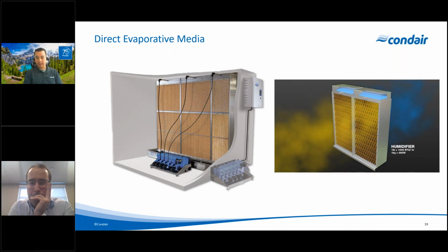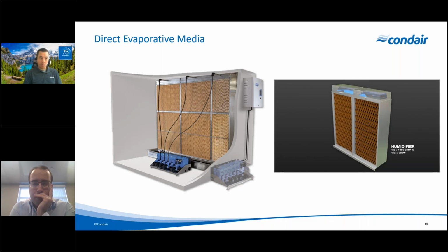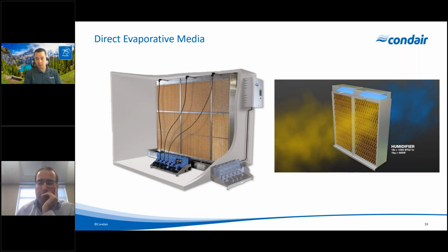But in terms of operation, water quality, and install, this is probably the most basic system that you can use when we're looking at adiabatic. The nice thing about it is, because it's an evaporative pad system, we can use any type of water. As long as it is drinking quality water, you can put the water through the system. And because all of the evaporation takes place within the pad itself, generally for a retrofit application, we don't need as much room as we would with, for example, a high pressure system that we'll look at later on.